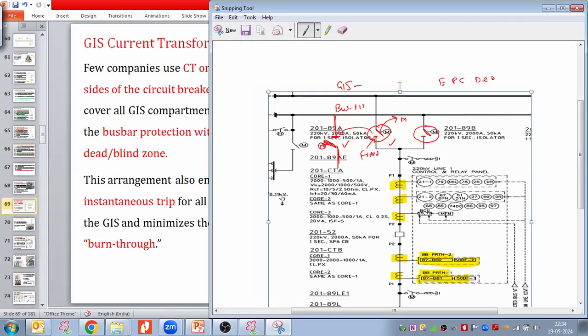Ideally, the moving part should be potential free, so it can close. If you take it here, it will always be at potential. So your moving part should be potential free, which means it should be opposite to the bus bar. Here, your moving part is not potential free; it is at 220 kV potential. So take the moving part towards the breaker side, where it is potential free. I am telling this because I have noticed that many EPC company design engineers prepare the SLD like this arrangement, which is not correct. This arrangement is correct. So after this class, do not repeat this kind of mistake in your SLD.